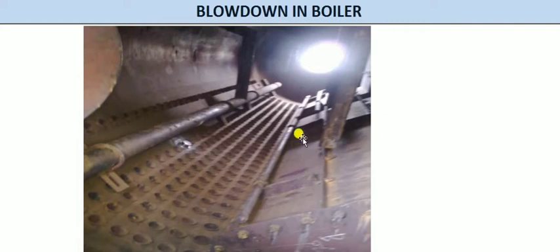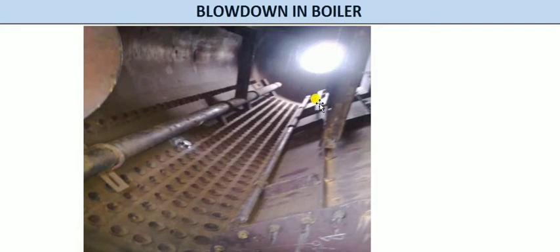Normally the flash steam will be used by the system when the steam quality is good; otherwise this steam quality can also affect other systems because the blowdown condensate concentration is higher. The valve opening on the continuous blowdown line will remain constant throughout the 24-hour operation — it will not be changed. Whenever there is a change in feed water quality or steam quality, we want to adjust it based on the calculation.